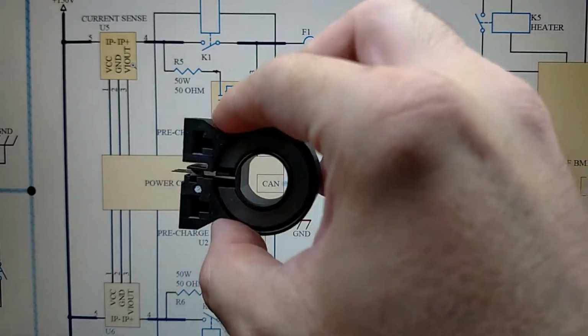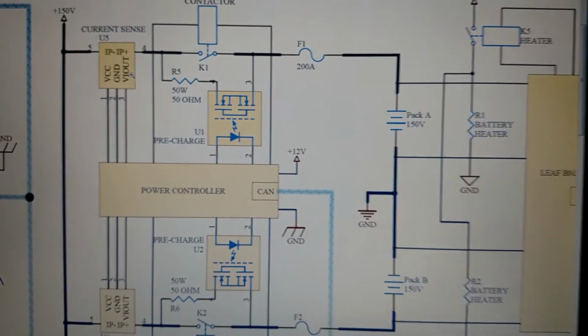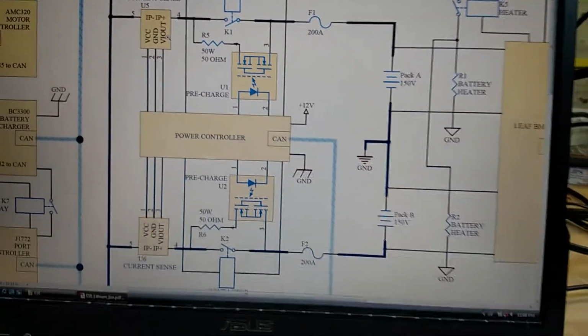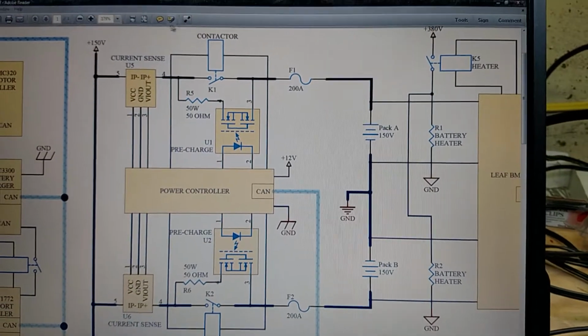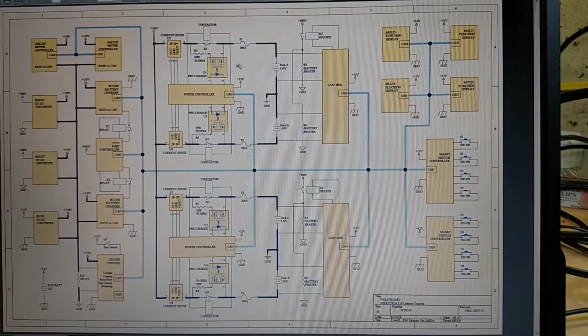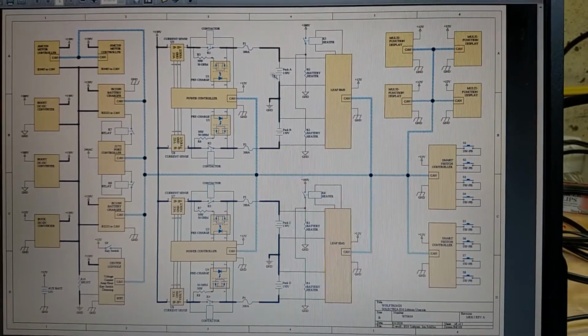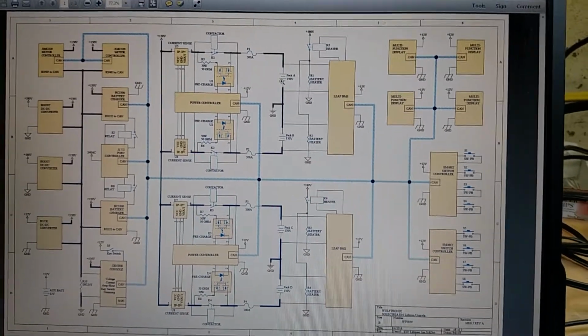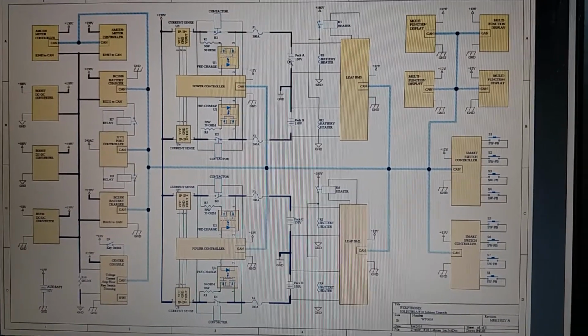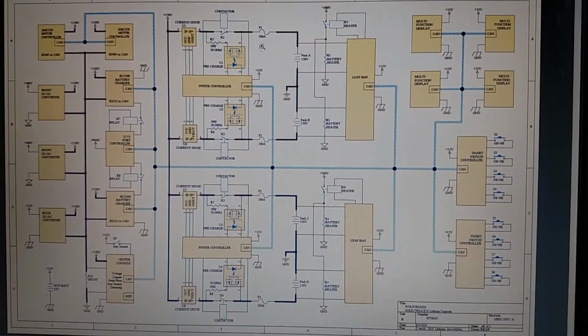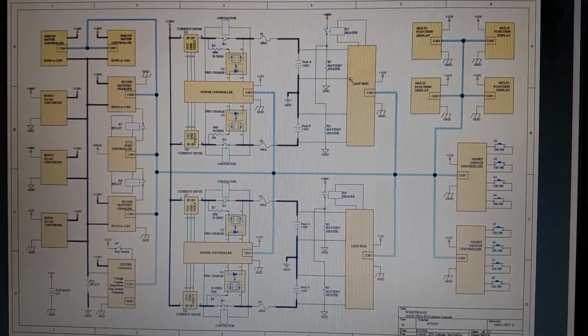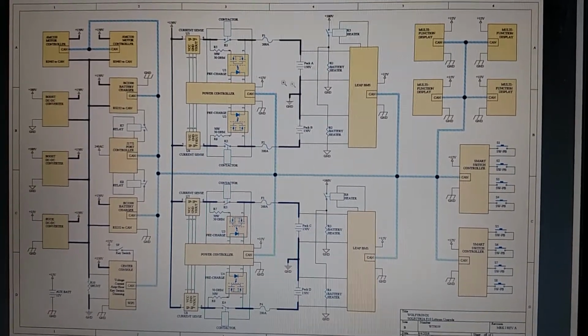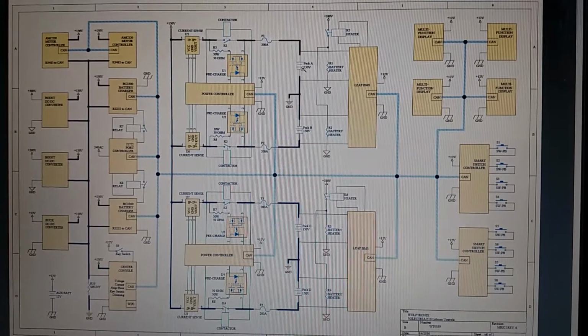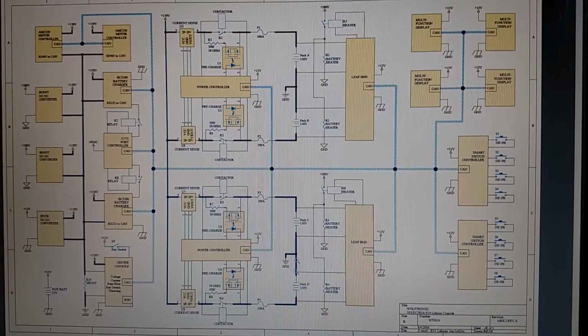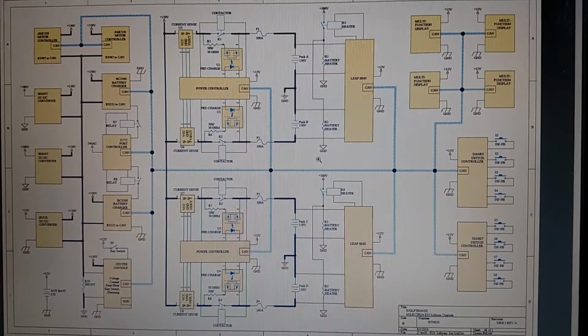The current sensors will be read by the power controller, and if it sees an imbalance of current, this power controller can talk to the other power controller and to the BMS. So if we're charging and one of the cells gets above 4.1 volts, it can open up that contactor to disconnect that pack, let the BMS do its balancing, and bring that cell back down while the others keep charging. Over time we'll get it all completely balanced out.